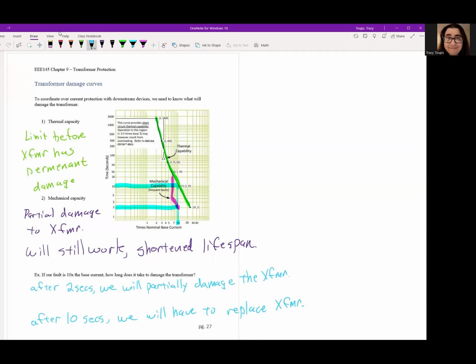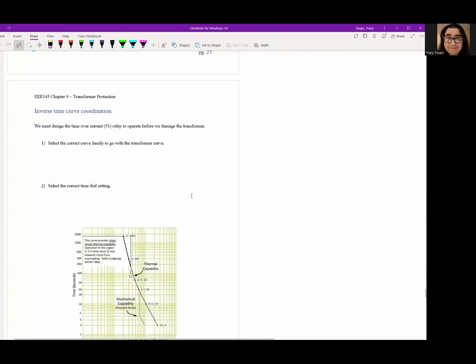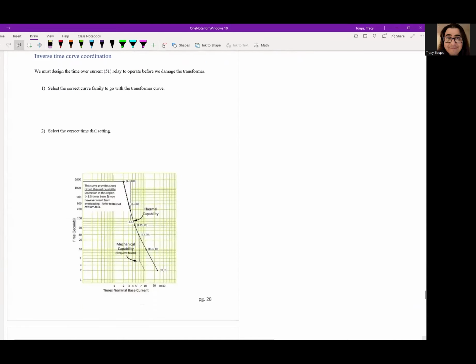Okay, so that's your 2 points you're looking at. You have that 2 seconds. Hey, we hit it. We need to stop right now. And 8 seconds go by, and then boom, the transformer's toast. Okay. Obviously, neither of these things should happen. We need to put protective devices in front of these curves so we never hit this damage curve for a transformer. Okay. So how do we do that? Well, we've been looking at time over current curves for quite a while. Let's remember how to do that.